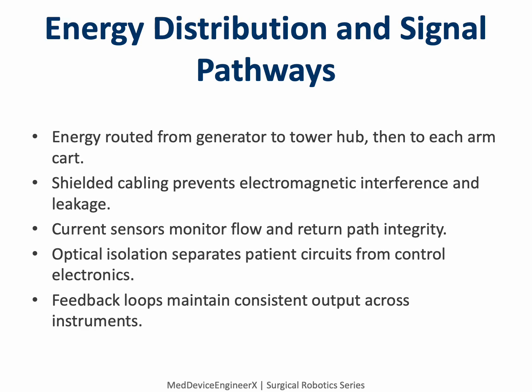Once energy leaves the generator, precision routing keeps it safe and efficient. Power travels through the tower's distribution board before branching toward the robotic arm carts. Each line is shielded to reduce electromagnetic interference that could distort imaging or data communication. Embedded current sensors monitor the flow continuously, confirming the energy returns through the patient return electrode or bipolar circuit without leakage. Optical isolators divide the high voltage and control domains, ensuring that no stray current can reach sensitive electronics or operators.